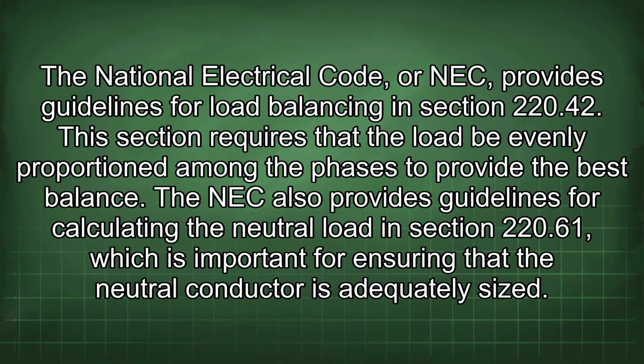The National Electrical Code, or NEC, provides guidelines for load balancing in section 220.42. This section requires that the load be evenly proportioned among the phases to provide the best balance. The NEC also provides guidelines for calculating the neutral load in section 220.61, which is important for ensuring that the neutral conductor is adequately sized.